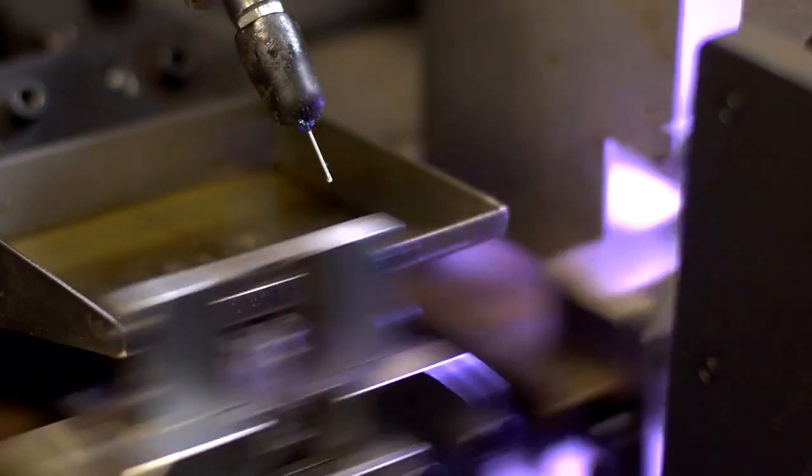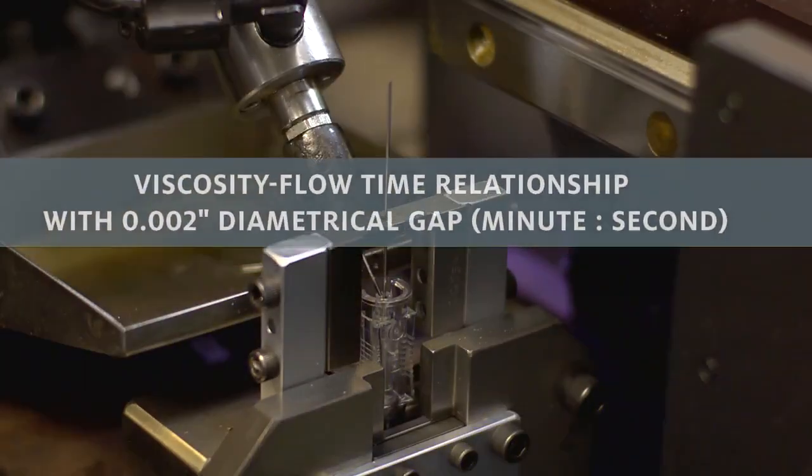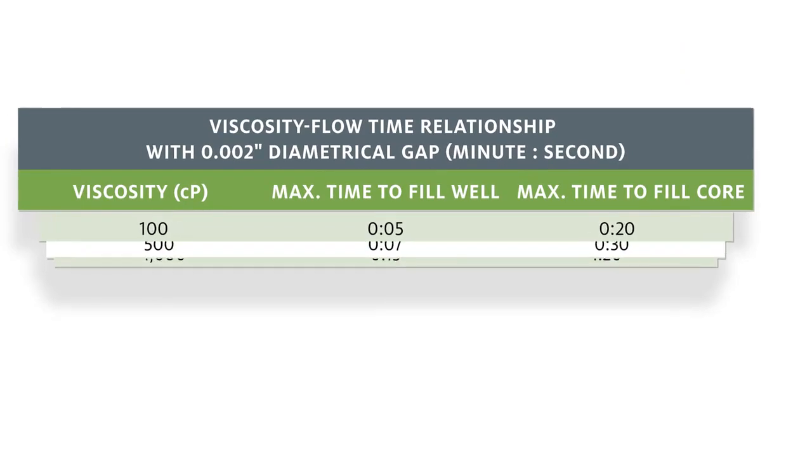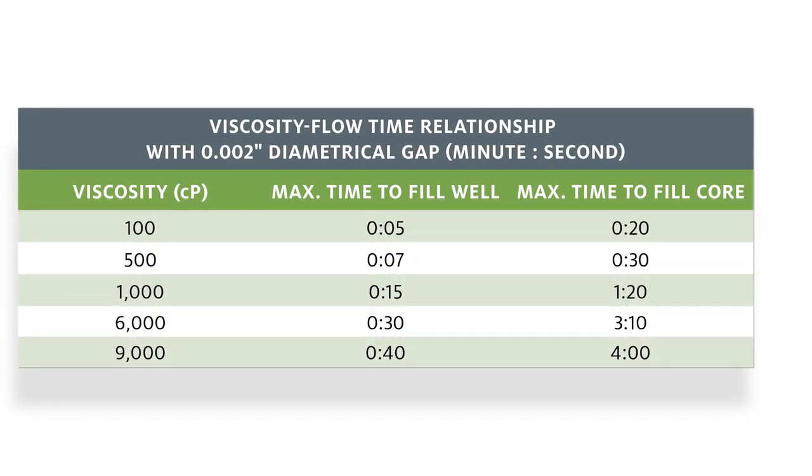Needle manufacturers may dispense adhesive on the cannula before it is inserted in the hub or into the well after the cannula is inserted in the hub. A pre- or post-application process dictates the recommended adhesive viscosity.